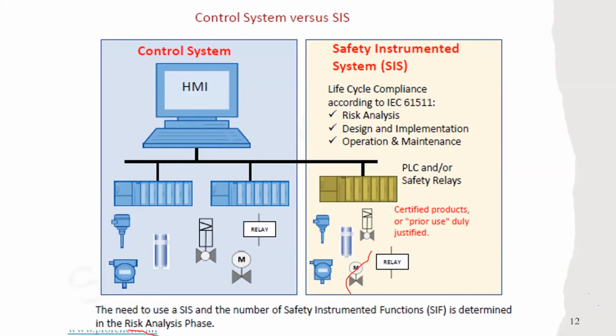But when you talk about the safety instrumented system, which deals with the safety aspect of your plant, it is compliant with the standard 61511. Risk analysis is properly done, design and implementation documents are available, procedures and O&M manuals are available. The PLC uses a particular kind of hardware and software which is certified according to the standard. So basically everything in the SIS follows the standard.